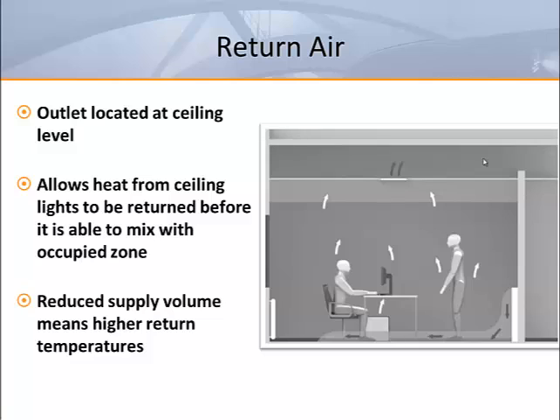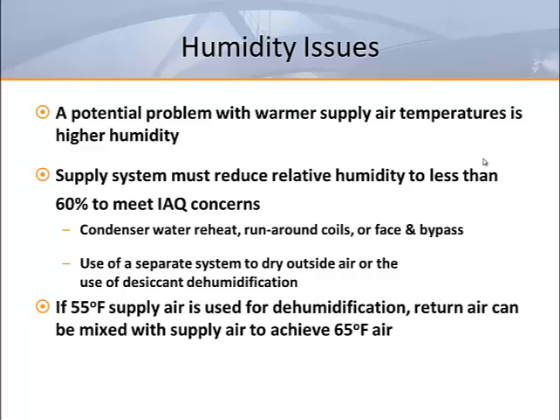In order for displacement to work most efficiently, the return air should be pulled from well above the occupied zone, preferably from the highest point in the room. Since much of the heat load from the overhead lighting is captured from above the occupied zone, the supply air temperatures are higher. You should expect higher return air temperatures than would be found in a conventional mixed air system. Humidity issues: in order to avoid potential humidity issues and air quality concerns, we need to limit the humidity to 60% or less. There are many strategies that we can employ at the air handler, or we might choose desiccant dehumidification. If we choose to drop our air temperatures to 55 degrees to wring out the moisture, we can blend the return air with the supply and bring it back up to 65 degrees.